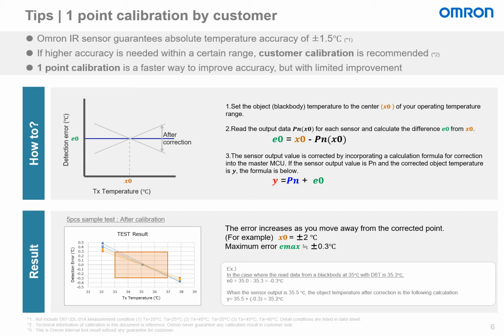The error increases as you move away from this corrected point. For example, at X0 plus or minus 2 degrees Celsius, the maximum error is about plus or minus 0.3 degrees Celsius. Because of the limited improvement that you will get from the 1-point calibration, it is recommended to use the 2-point calibration for better results.